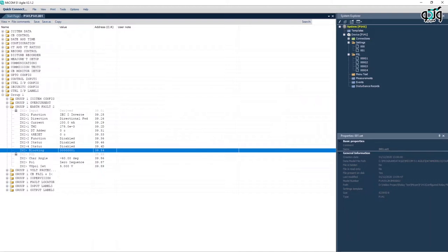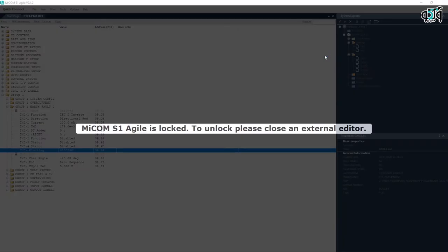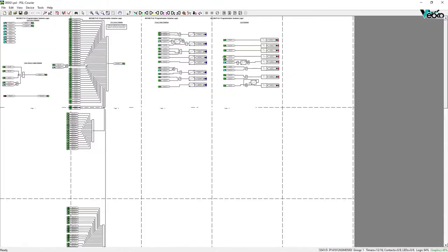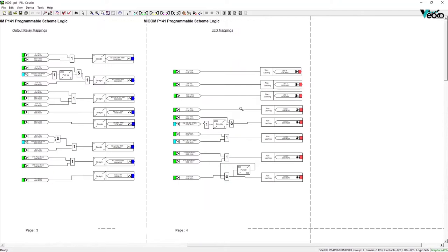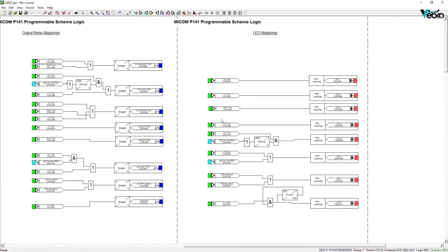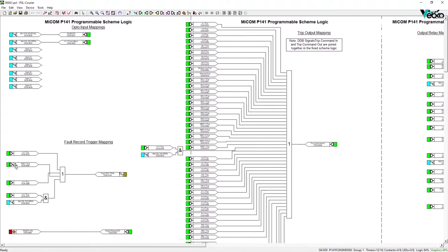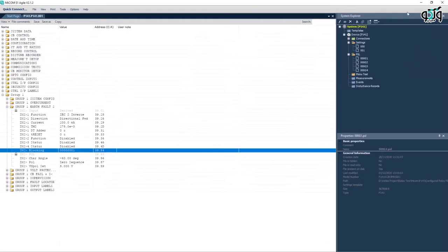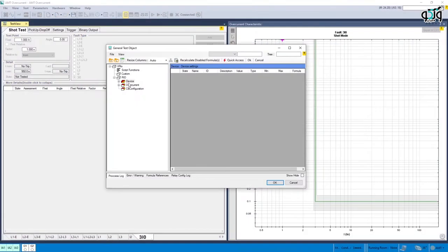Before considering any case, it is examined to see which output and LED are used for the performance of directional residual current protection. To do so, PSL or programmable scheme logic is used. It is possible that a separate contact is considered for the performance of each phase. Also, fault trigger record activation is checked with this factor as well.